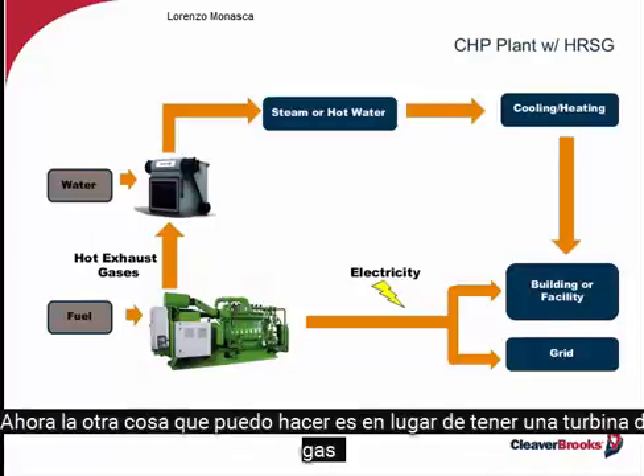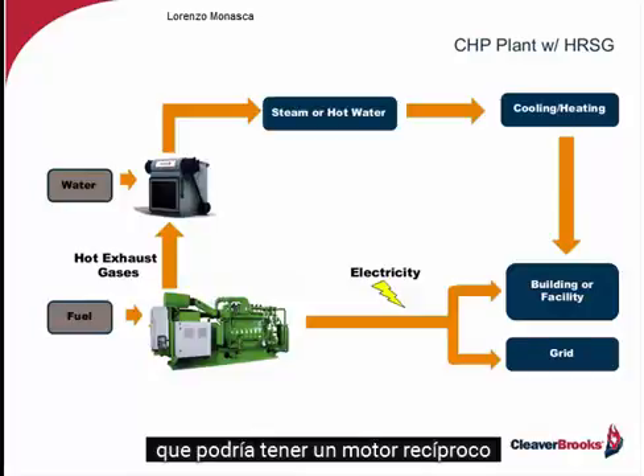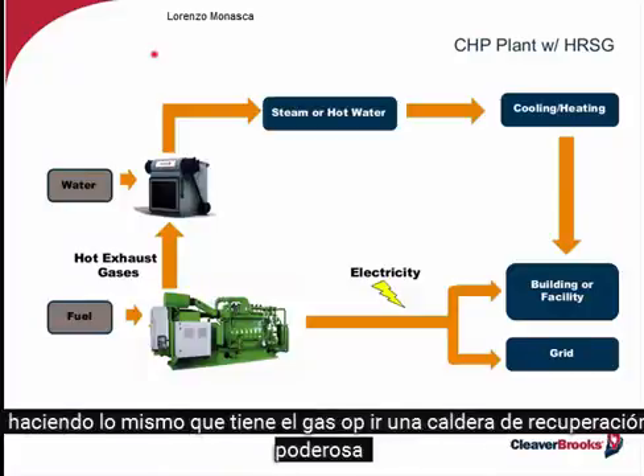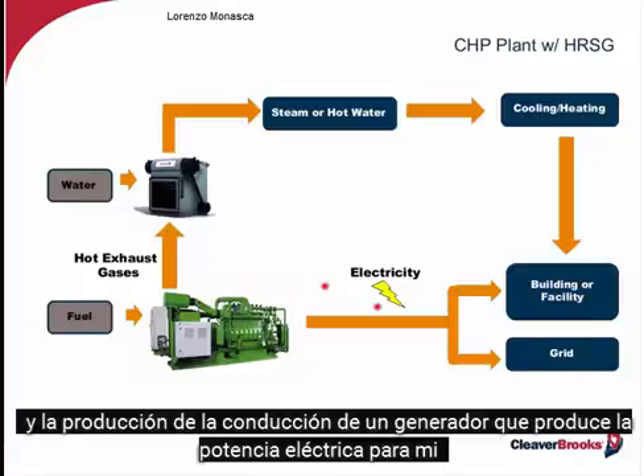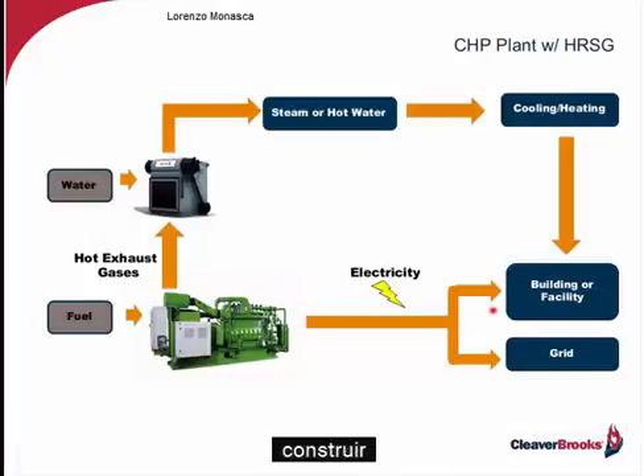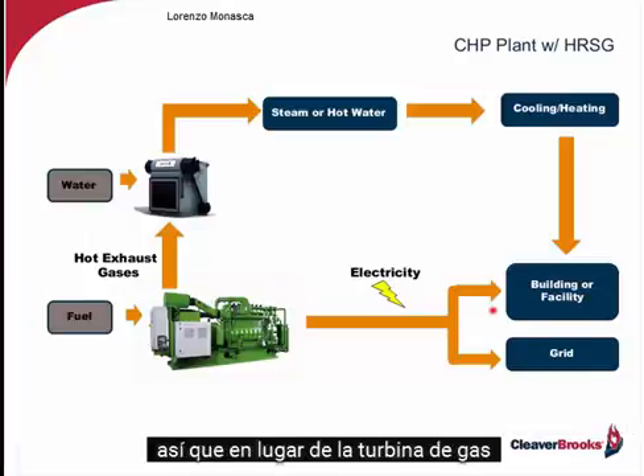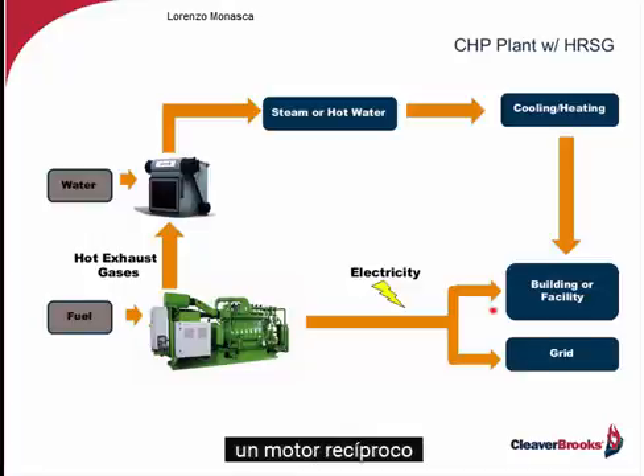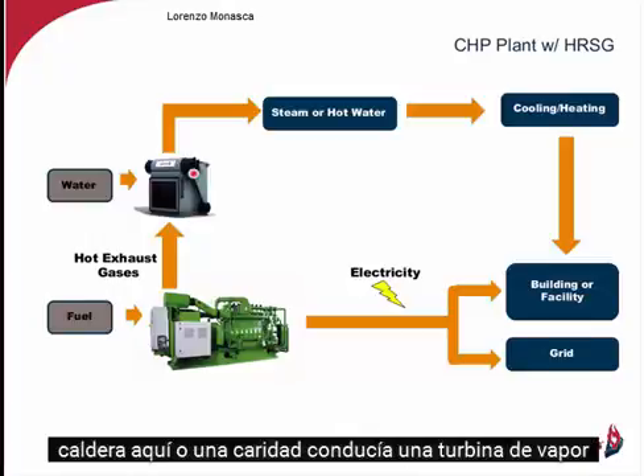Now, the other thing I could do is, rather than having a gas turbine, I could have a reciprocating engine doing the same thing. It's got the off gas going to my heat recovery boiler, HRSG, and driving a generator, producing the electrical power for my building. So rather than the gas turbine, I'm using a reciprocating engine. This is then called combined heat and power, or a combined cycle, if this boiler here, or HRSG, was driving a steam turbine.